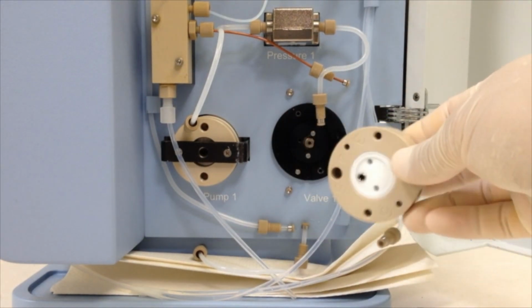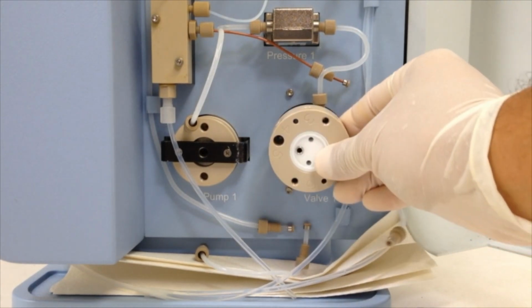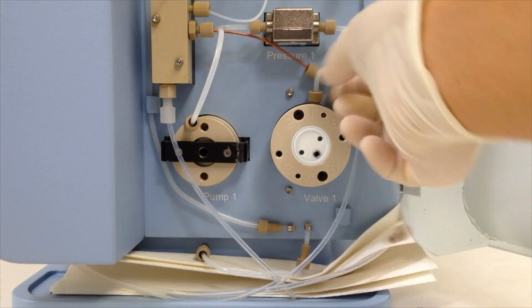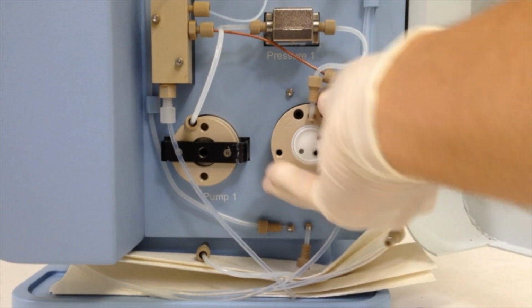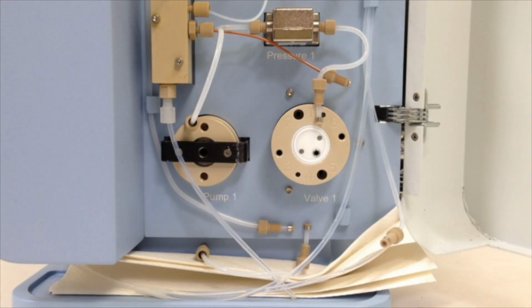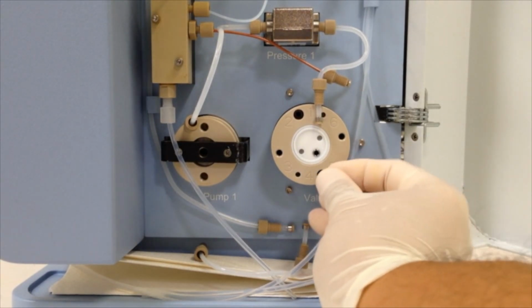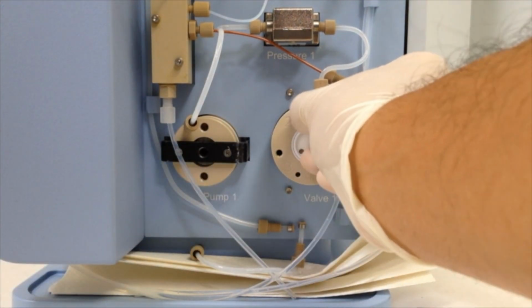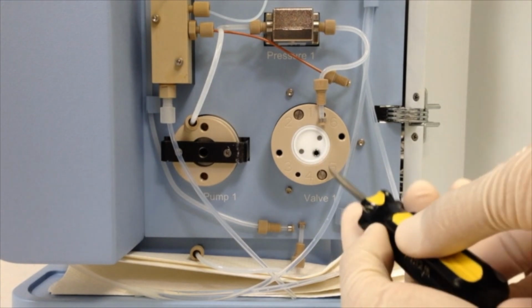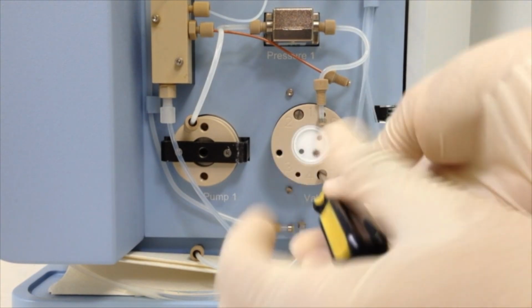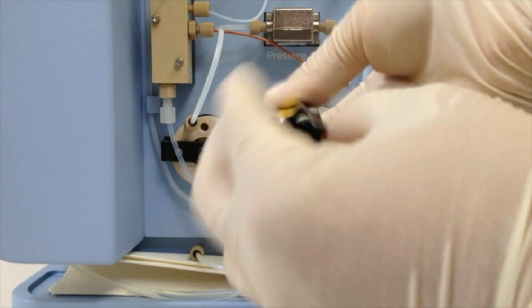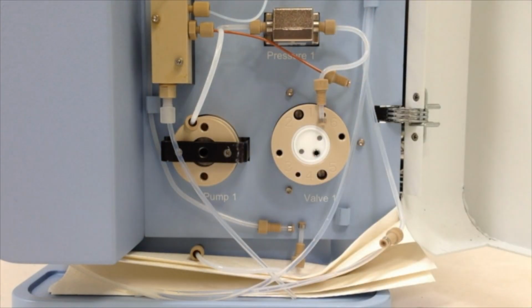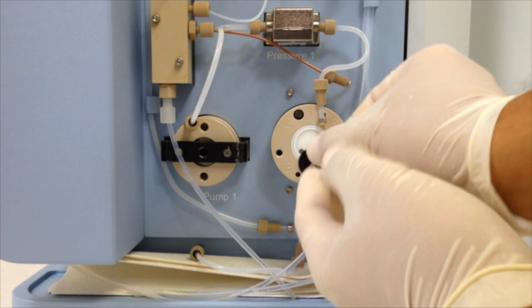Line up the prongs of the valve motor with the valve insert, and then slide the valve onto the prongs. Turn the valve so port 1 is at the top, and then push the valve face all the way back onto the valve motor. Screw in the 2 shoulder screws to secure the valve face to the valve motor. Be careful not to over-tighten the 2 shoulder screws, as these can break easily. Screw on the valve indicator plate to the valve face.